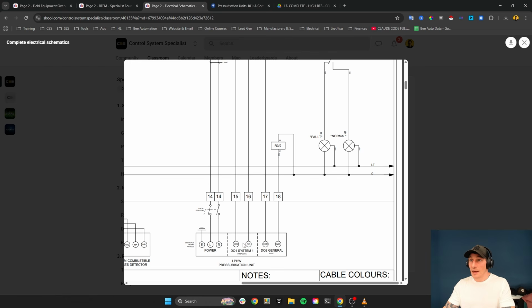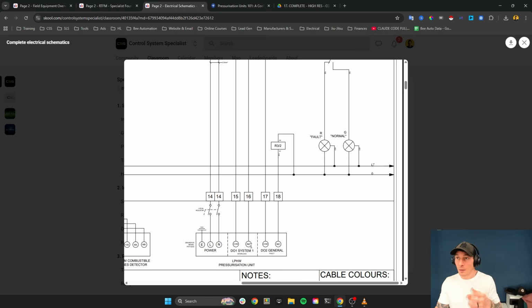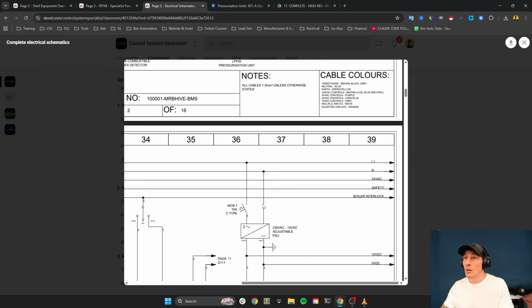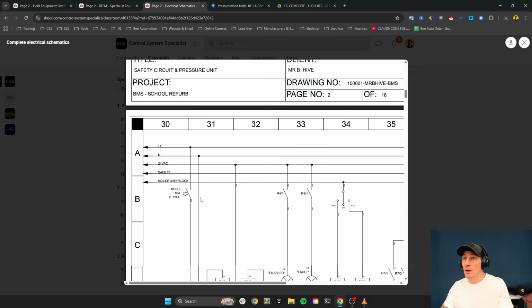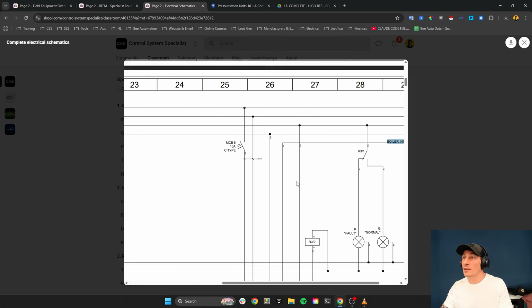So this needs to be in a healthy state based on those things that I just listed, to send that, or relay, this is where the word relay comes in, relay that 24 volts AC down the system further on this boiler interlock circuit, which then you can see boiler control is picked up off that interlock circuit.